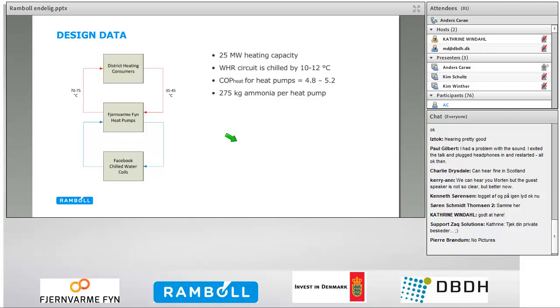The 9 heat pumps that have been installed at this stage can deliver around 25 megawatt of heat, which is just under 3 megawatts per heat pump. On the waste heat recovery side, the water is chilled by 10 to 12 degrees through the heat pumps before it is pumped to Facebook. On the district heating side, the return temperature varies between 35 and 45 degrees Celsius, depending on the time of the year, but should usually be around or just under 40 degrees Celsius. The supply temperature for the heat pumps is between 70 and 75 degrees Celsius, depending on the district heating requirements.